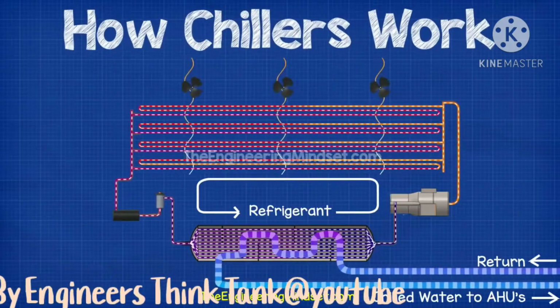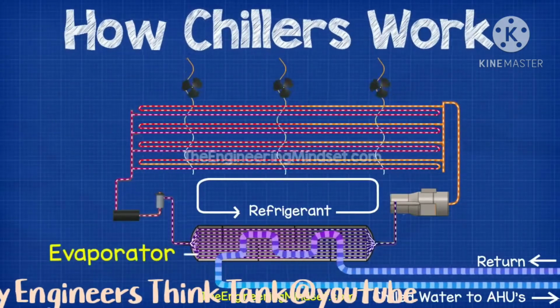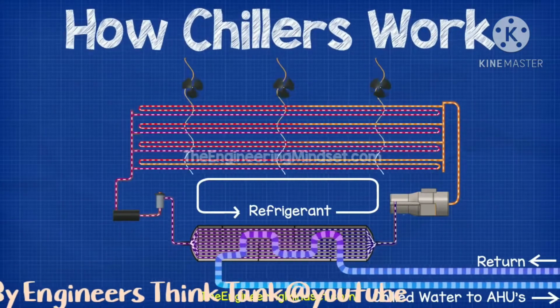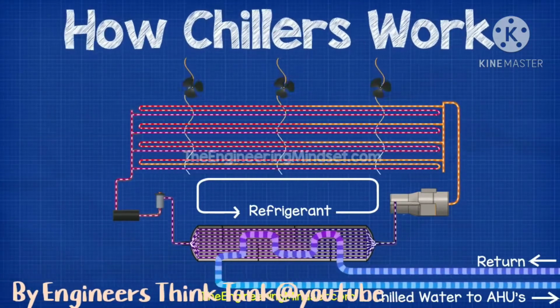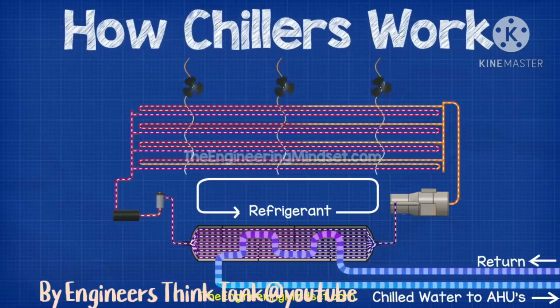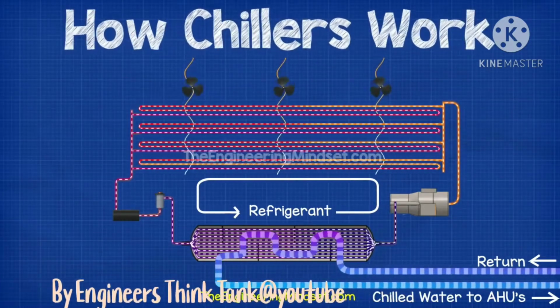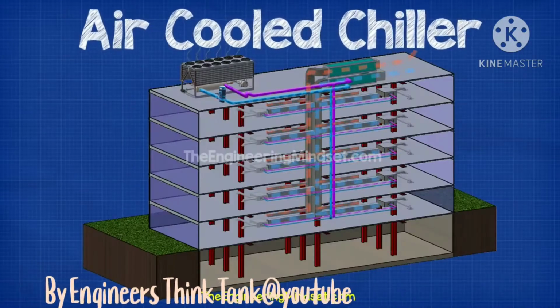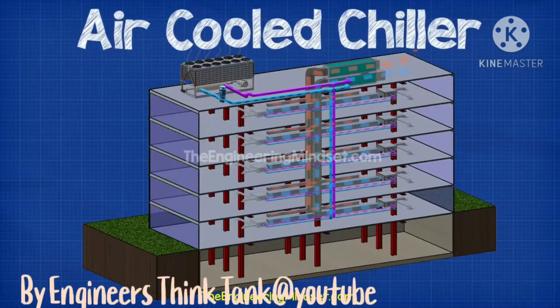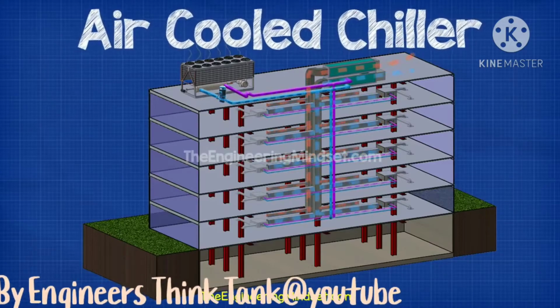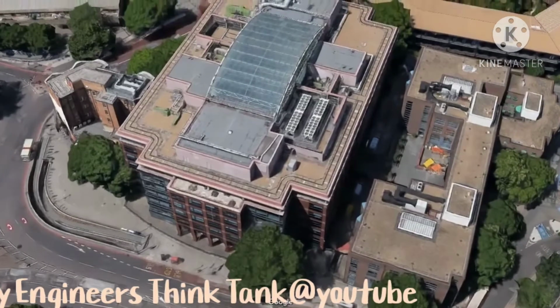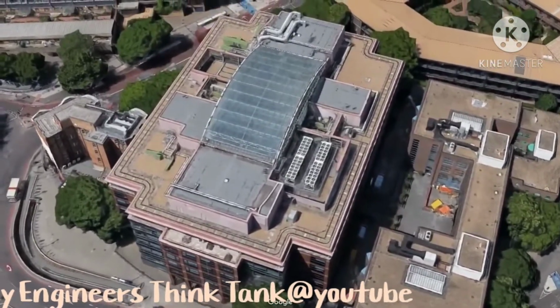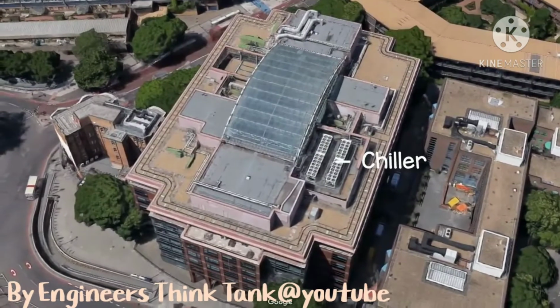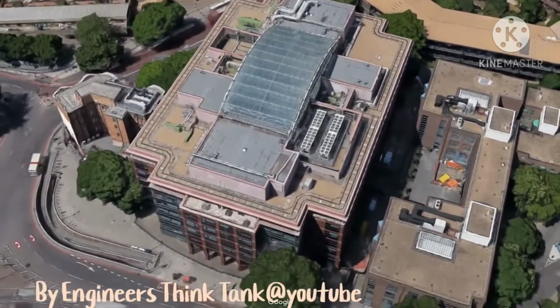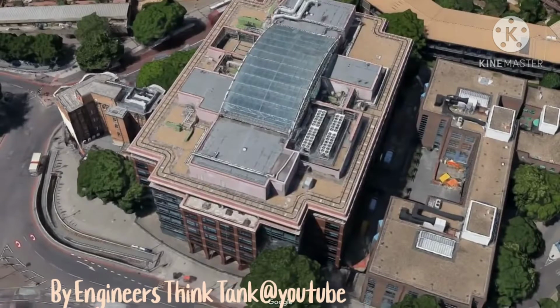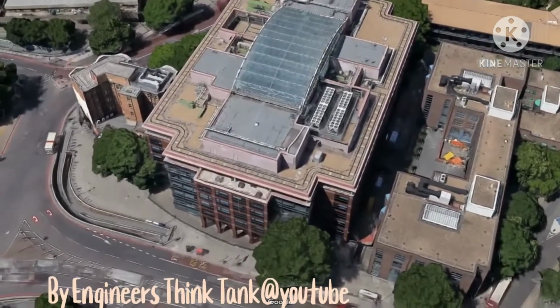This unwanted heat is again transferred over to the condenser of the chiller from the evaporator. It is transferred via a refrigerant, which loops between the evaporator and the condenser and is forced by the compressor. The difference with this type of chiller is that the fan blows air across the condenser, which removes the unwanted heat. So in this instance, the condenser of the chiller has been cooled by air, therefore it is an air-cooled chiller. Air-cooled chillers are typically located outside because they need access to a lot of ambient air in order to reject the heat. This type of chiller can usually be found on medium to large commercial property, and there's an example on screen now of how these units look in the real world on the roof of an office.